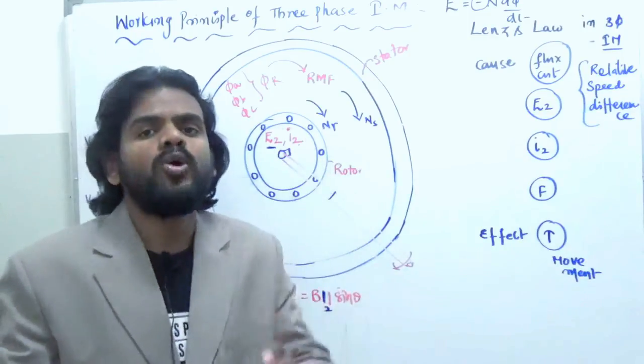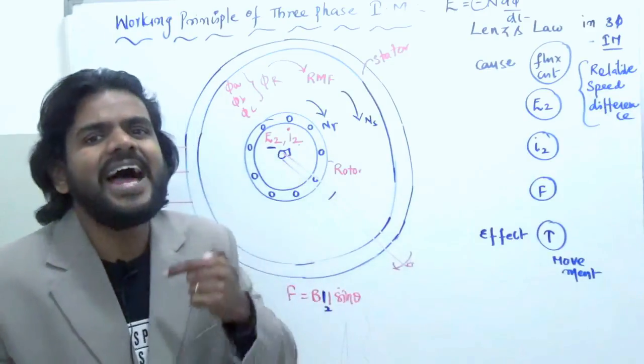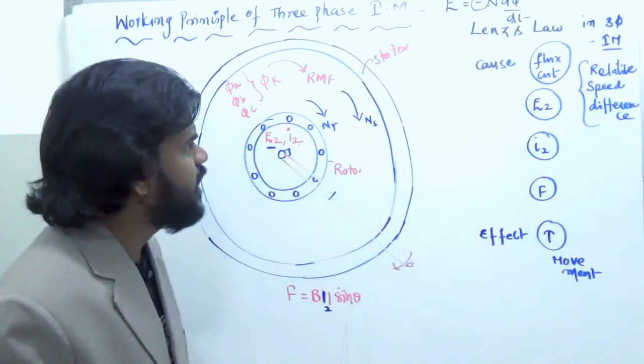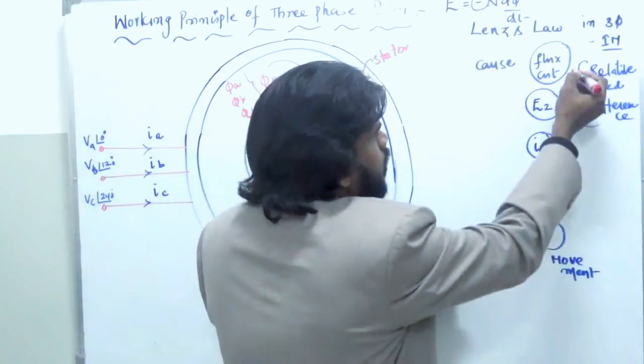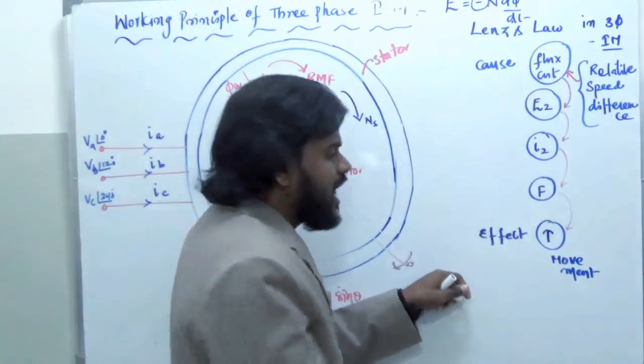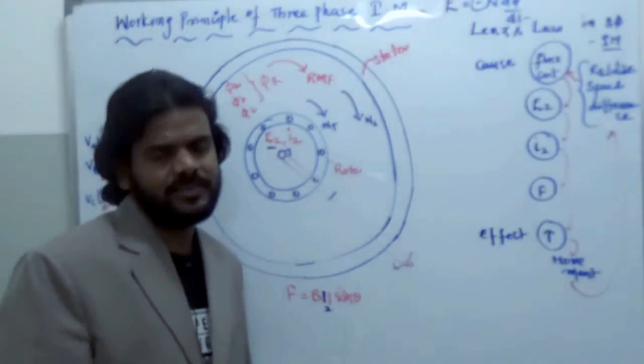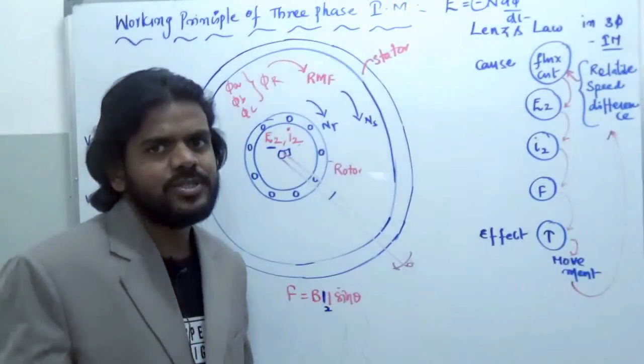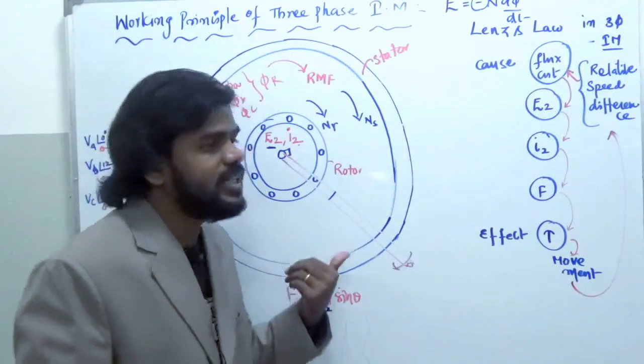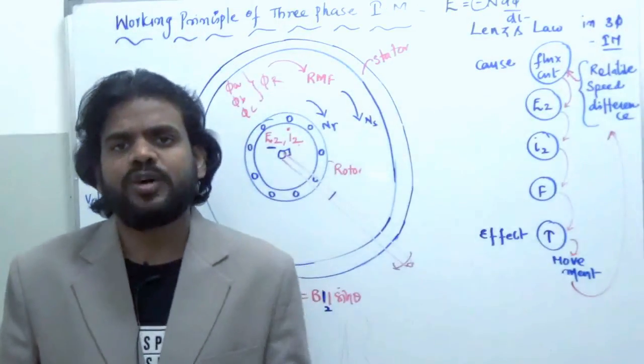That's the reason why the rotor rotates in the same direction as the stator. To summarize: relative speed difference is the reason for flux cut, flux cut is the reason for E2, E2 is the reason for I2, I2 is the reason for force, force is the reason for torque, torque is the reason for movement, and movement opposes the relative speed difference. So the rotor tries to run in the same direction as the stator and tries to catch it.